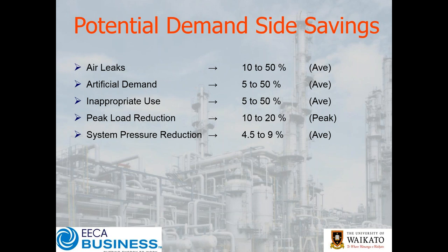If we drop our discharge pressure at the compressor from, say, seven-and-a-half bar to six-and-a-half bar — a one-bar reduction — the compressor is working a lot less hard, which means you'll reduce your power consumption. Depending on the compressor technology, as a rule of thumb we work on between six and nine percent power reduction if you drop that one bar at the discharge pressure on the compressor.